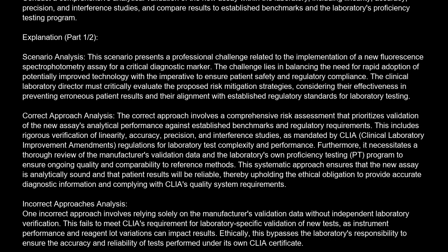Correct approach analysis. The correct approach involves a comprehensive risk assessment that prioritizes validation of the new assay's analytical performance against established benchmarks and regulatory requirements. This includes rigorous verification of linearity, accuracy, precision, and interference studies, as mandated by CLIA, Clinical Laboratory Improvement Amendments, regulations for laboratory test complexity and performance.